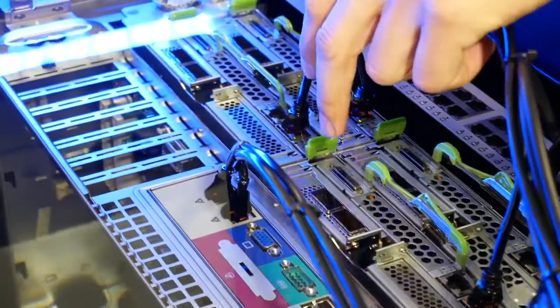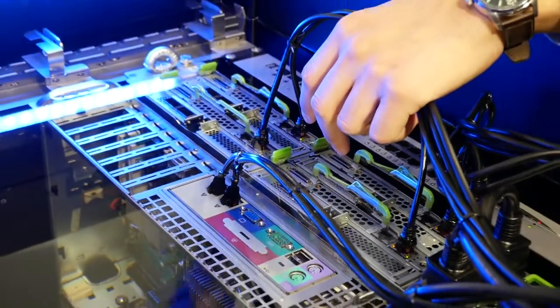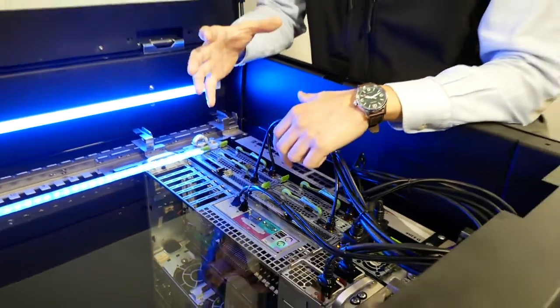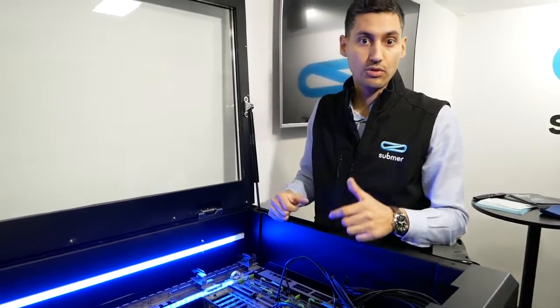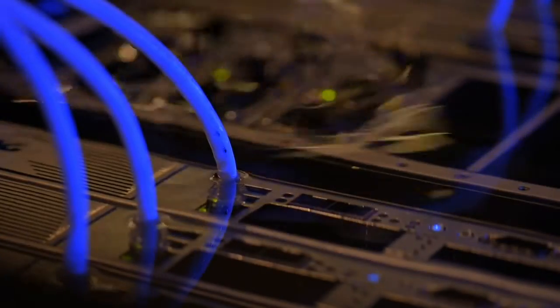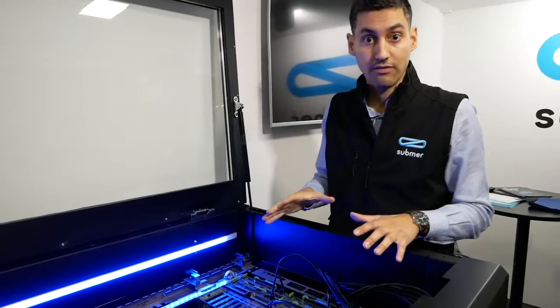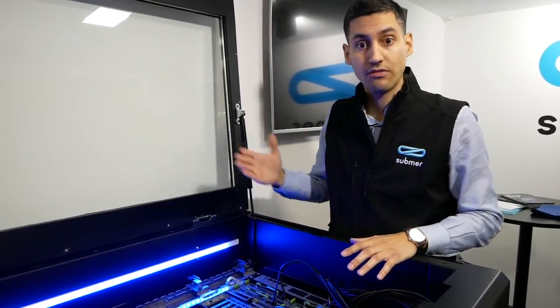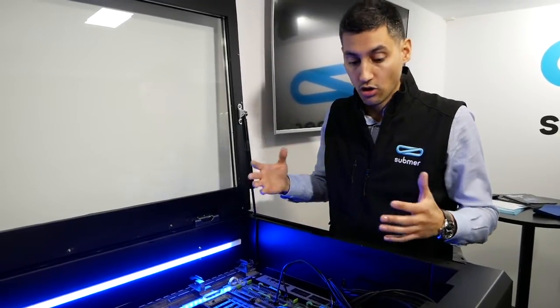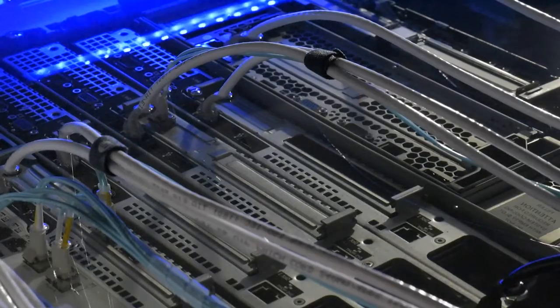We've been able to efficiently move this fluid around the tank, thanks to what we call the cooling distribution unit, which I will explain now. We monitor the fluid with digital sensors — temperature, flow rates, level sensors — and move the fluid around so that we capture the heat in the most efficient way. With this, we are able to save more than 95% of the cooling costs for the data center, making much more efficient operational costs and expenses.